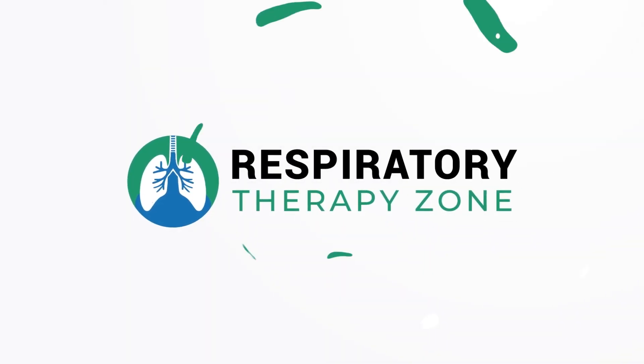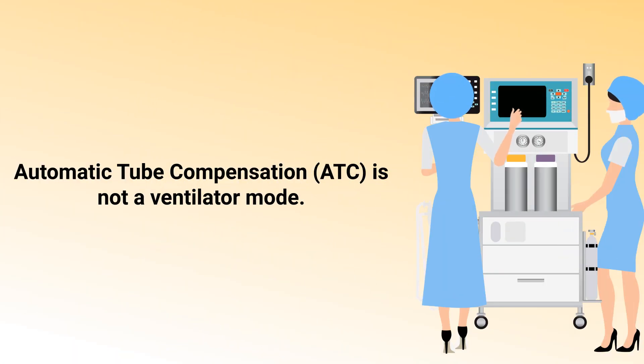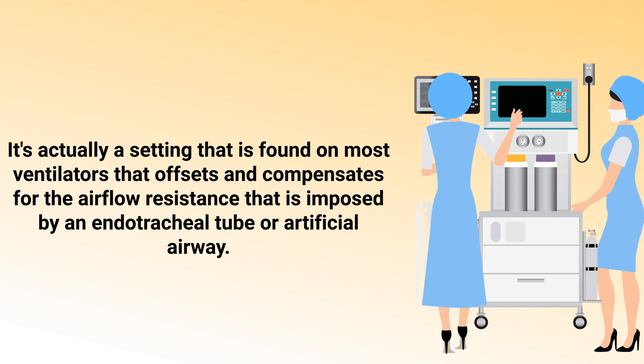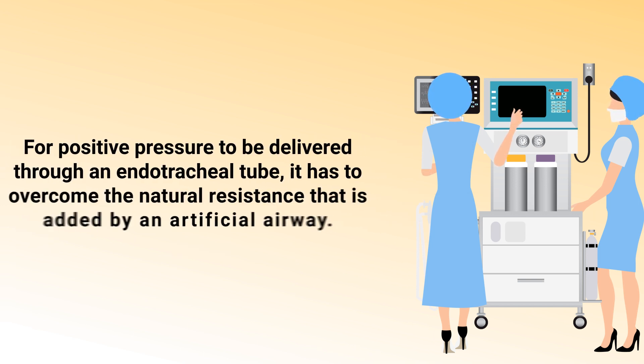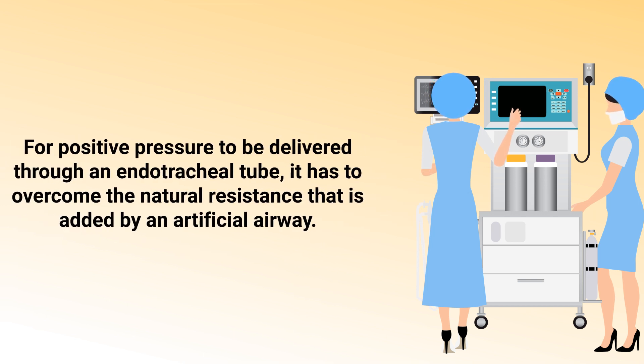Technically speaking, automatic tube compensation is not a ventilator mode. It's actually a setting that is found on most ventilators that offsets and compensates for the airflow resistance that is imposed by an endotracheal tube or artificial airway.